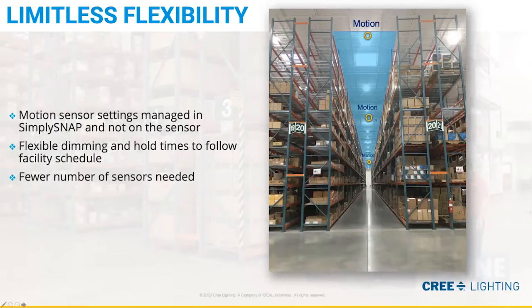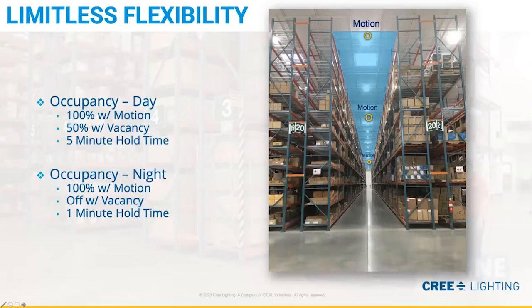If you look at this example, this is from a Uline warehouse. And over here, we've got a sensor on each end of the aisle and one in the middle, instead of having one on every light. So if a fork truck comes down the aisle from either side, all of the lights in that zone are going to go to their configured occupancy dimming level. In addition to that strategic placement of occupancy sensors, the configurable hold times and dimming levels are done within SimplySNAP rather than on the sensor.